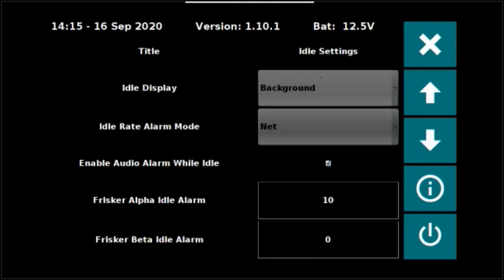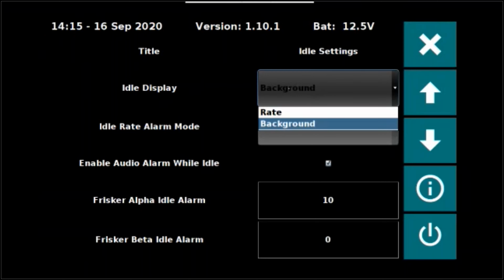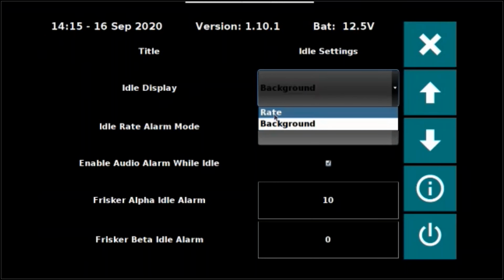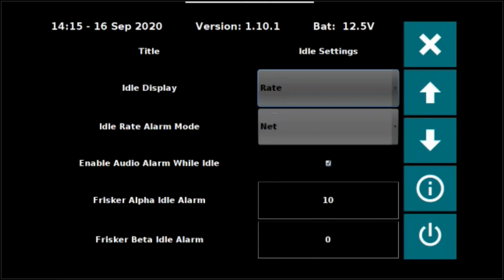Here you can set the idle configuration. Currently it's set to background average. That's the 5-minute rolling background that it has for the average rate. You can also select the background rate, which is a fairly instantaneous rate reading. And in here you can set the alarm points for both the alpha and beta readings for whatever the idle setting is. Next page.